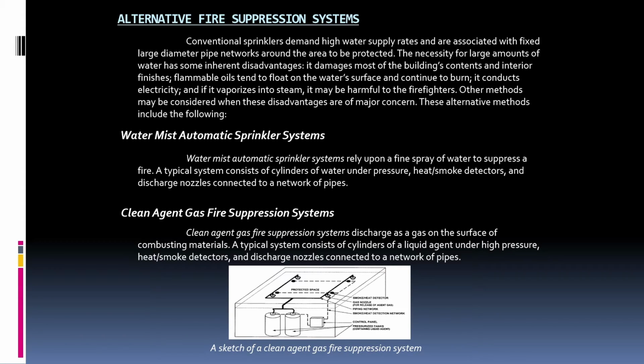The ability of small droplets to absorb heat and create steam at the fire source is the key to the effectiveness of fine mist systems in controlling and extinguishing fires. This process makes water mist systems more effective than a conventional automatic sprinkler system. But like conventional systems, water mist systems cannot be used on water-reactive materials.